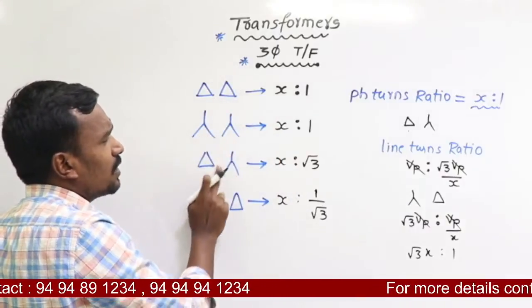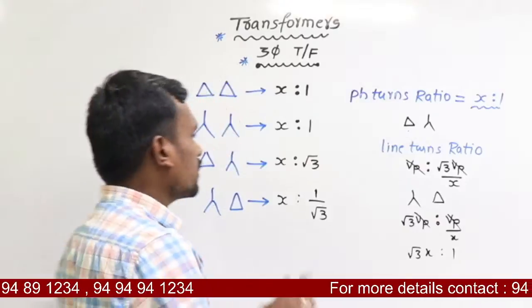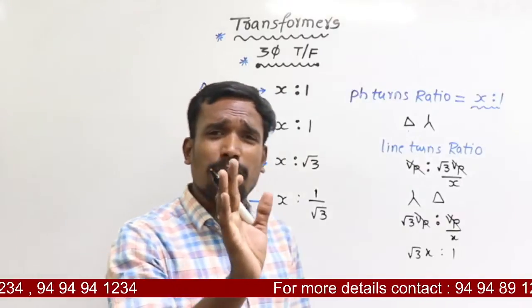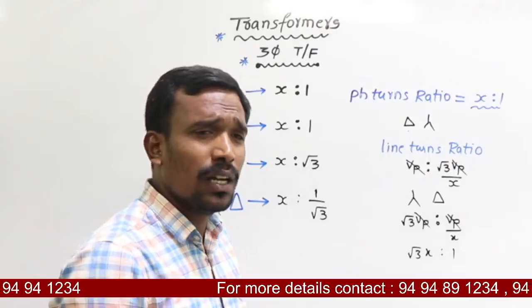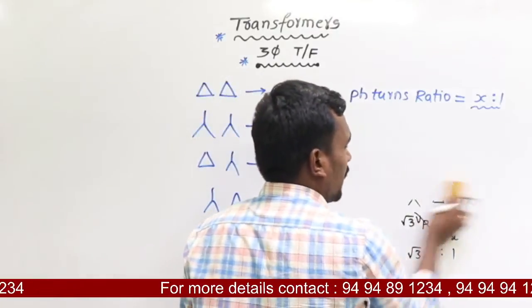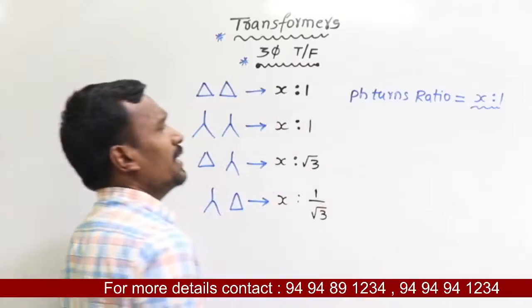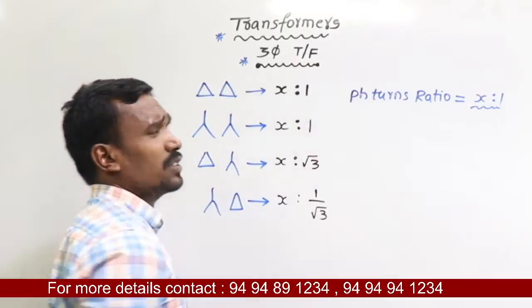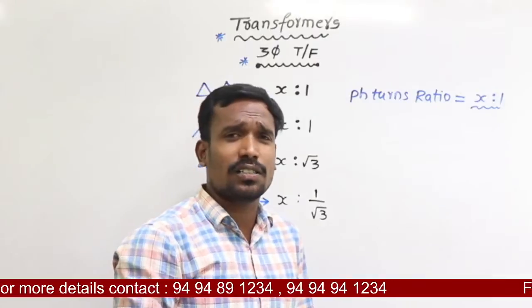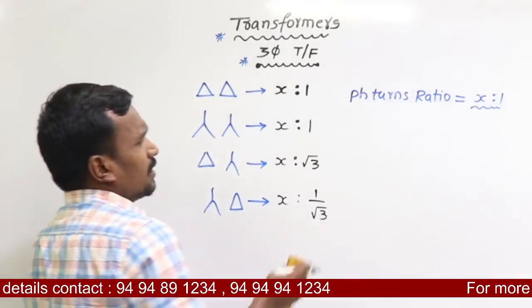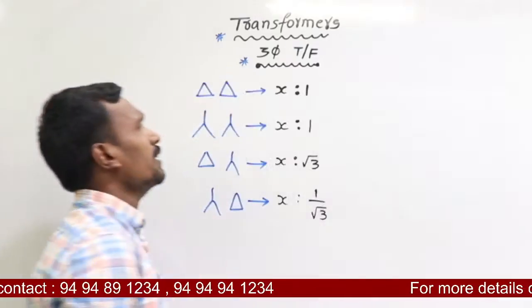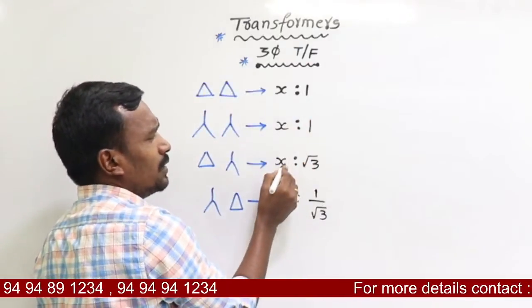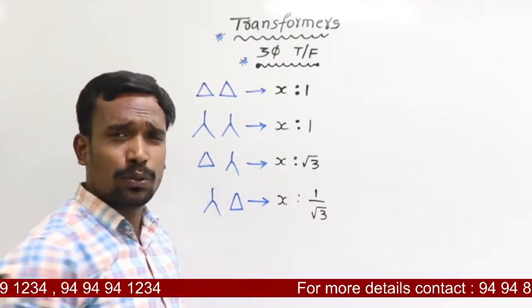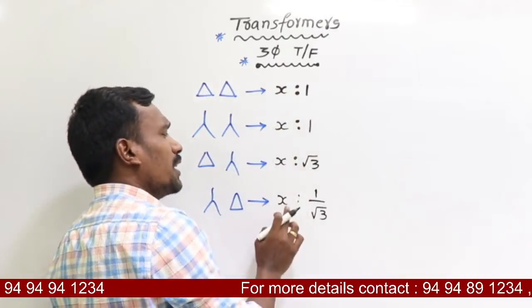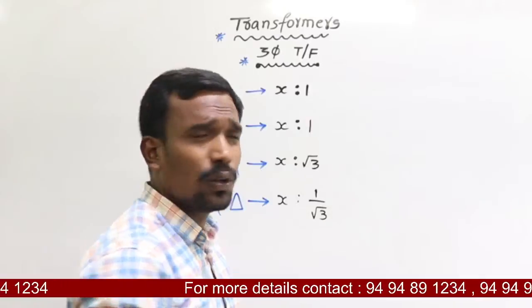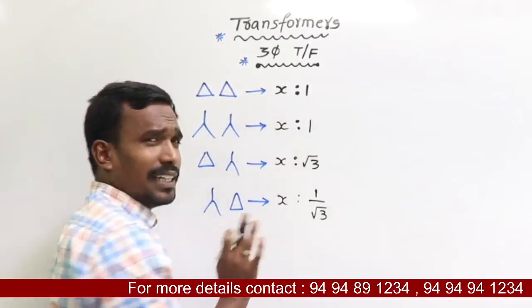Based on this we conclude some points about the line turns ratios and phase turns ratios for delta, star, and delta-star, star-delta. For the same phase turns ratio, the line turns ratios are: x is to 1, x is to root 3, and x is to 1 by root 3.